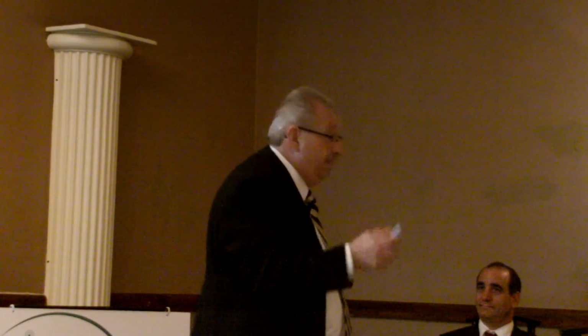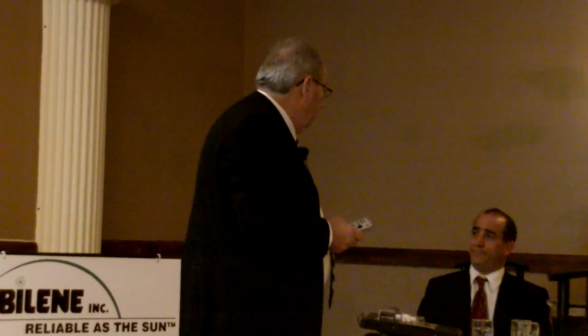Yes, sir. So you say for 9 years we had draft? And we passed. No, we never had draft, and we passed. Maybe the inspector didn't really check it. Maybe he came in and we had it running low fire. I know why you couldn't figure it out, because the draft holes in the back were covered by the wall. You couldn't get your tool there.